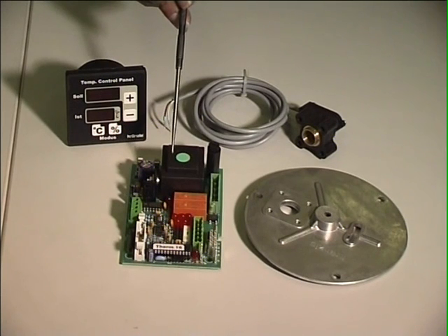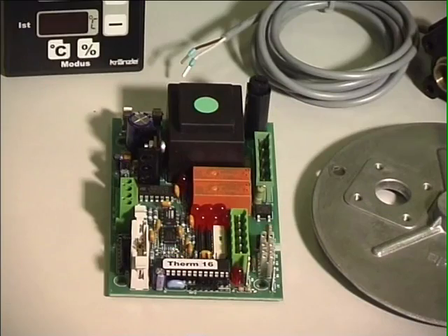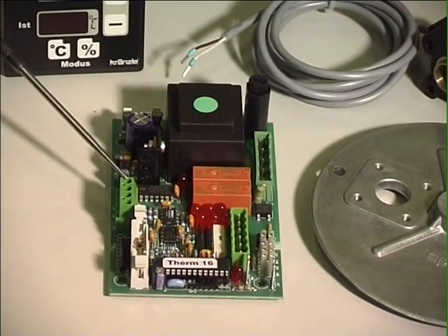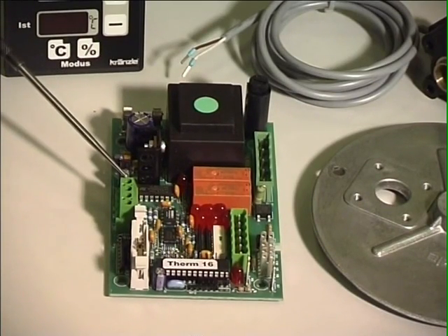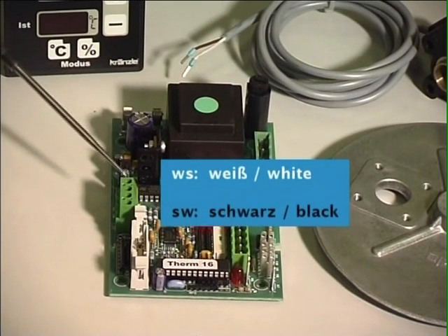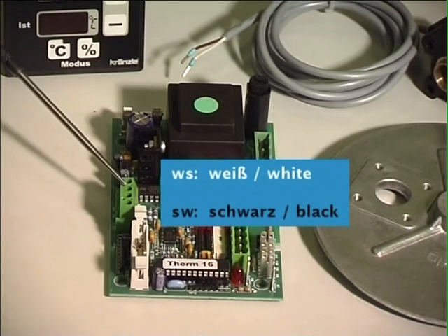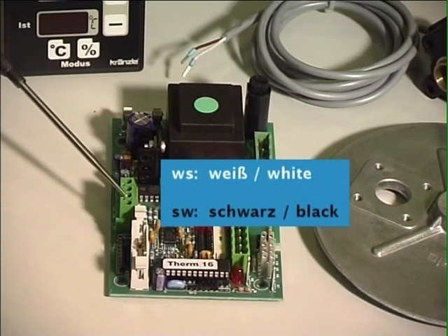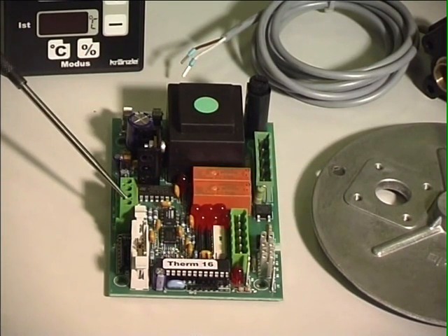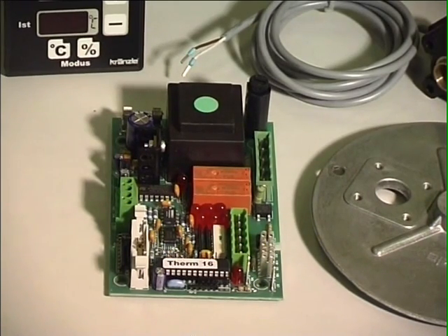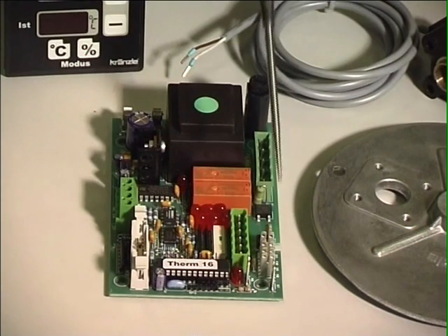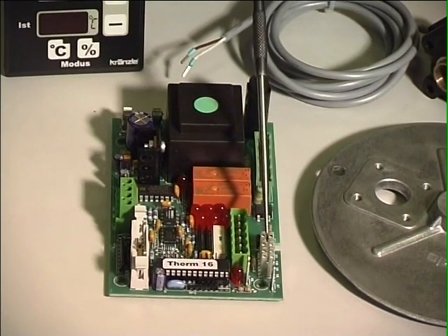When you transform a machine, you must make sure that the contacts for the temperature probe are connected here. White cable to terminal 1, black cable to terminal 2. The photocell must be connected here. These terminals are not occupied because they are foreseen for special functions.